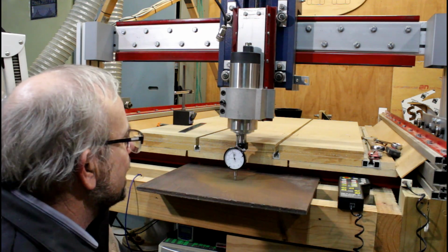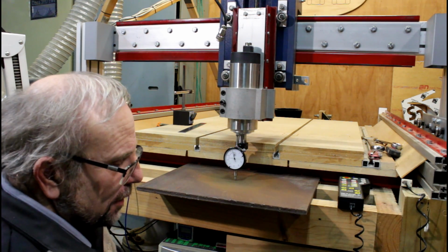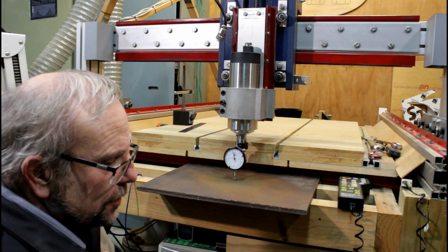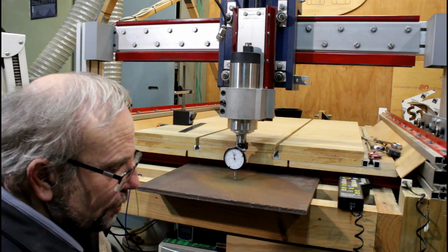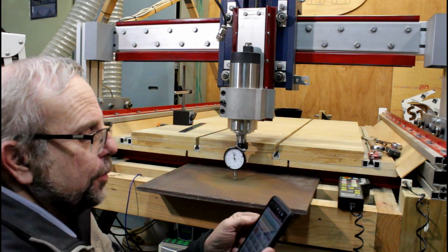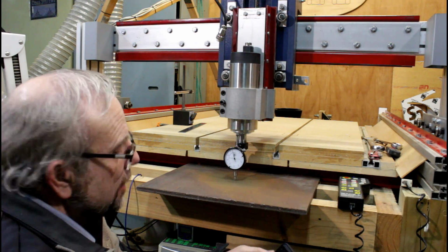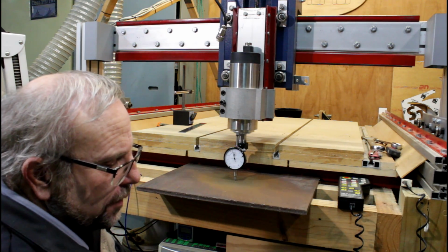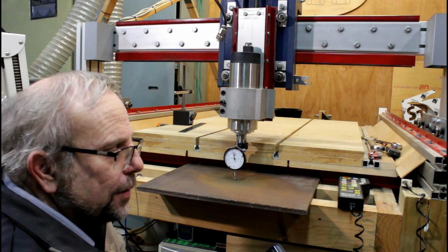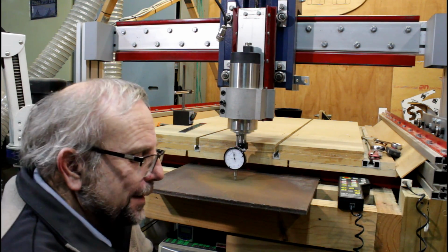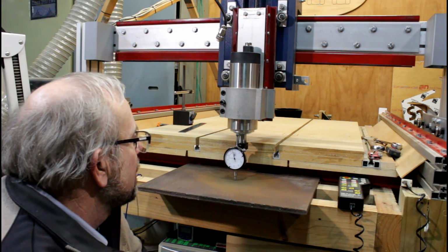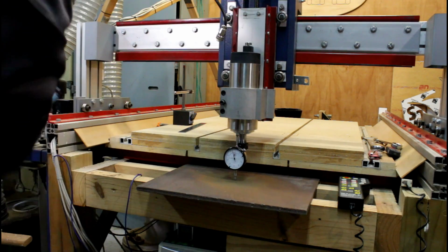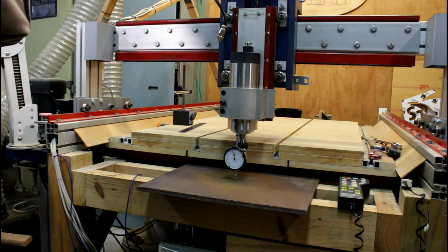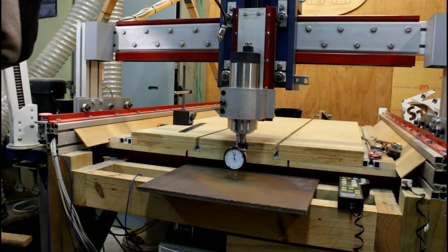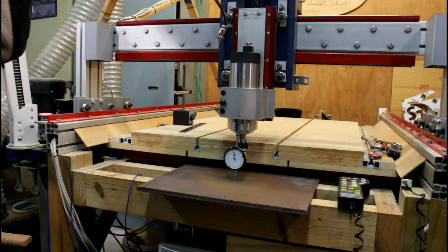So I need to do a bit of a calculation and work out how many millimeters that is, so that I can enter that into my software. So 1 inch minus 0.0035 is 0.9965 inches, and multiply that by 25.4. So I've moved 25.3111 millimeters. So I'm going to enter that into the calibration software: 25.3111. It's recalculated things for me.